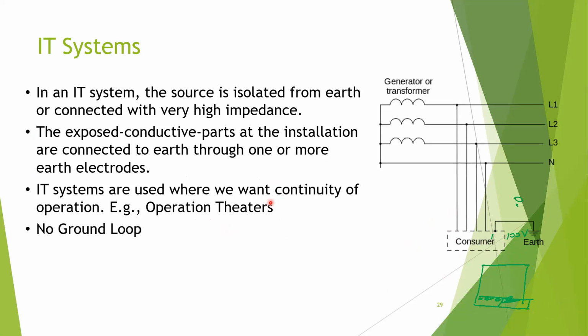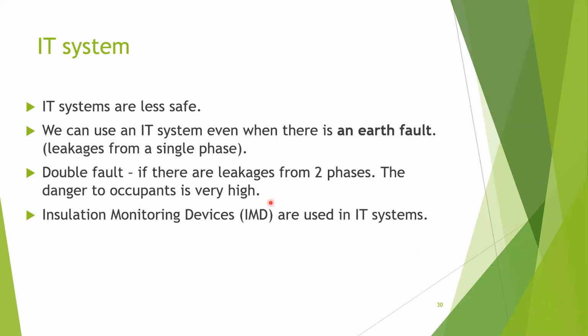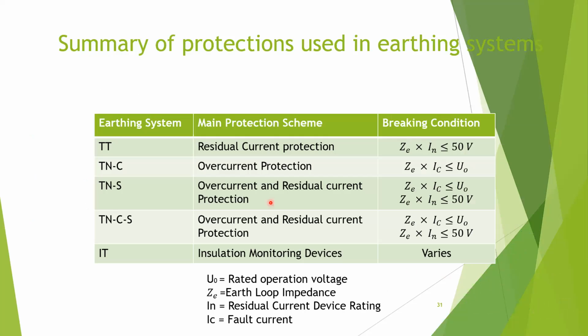So those things are the characteristics of IT systems. And this is the summary of earthing systems. So these are the equations. This is just the equation we had. The breaking condition, so this is the breaking condition for RCD. So you can use RCD. You may remember this equation: IΔn is smaller or equal to 50 over ZE. ZE is the loop impedance. So this is the breaking condition.